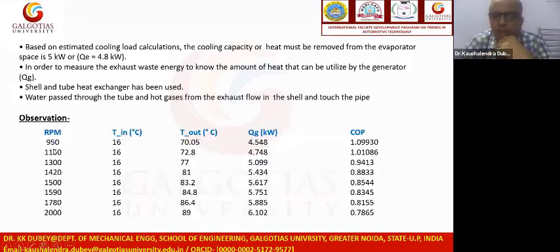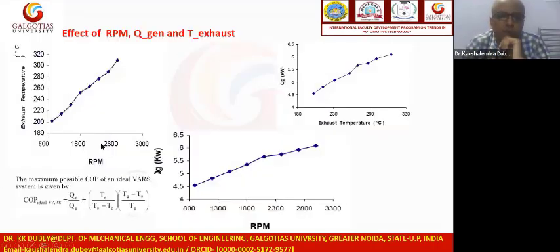The reason is this: after a certain level, the energy is going to waste. That higher energy is not on the useful side. So we cannot go for the higher RPM for the cooling achievement. We must maintain the recommended COP for the VAR system. Here some real-time graphs are also available. We can see that as the RPM increases, the exhaust temperature increases. Furthermore, the temperature and the QG increase, but we cannot achieve more COP. So for the COP, we need to fix the temperature of the generator. We need to fix the temperature of the absorber.